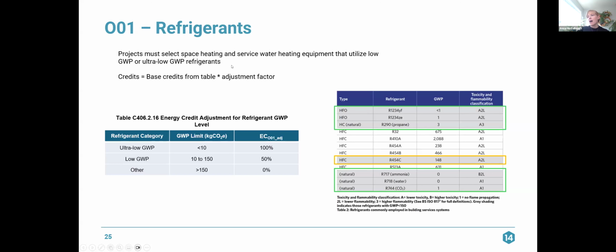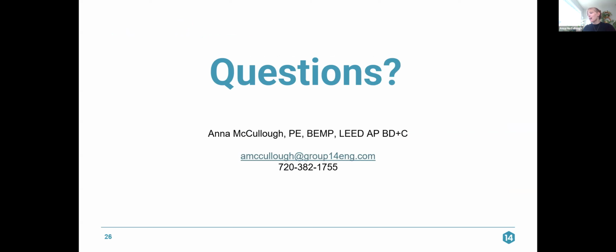And then the ultra low GWPs are going to be these: propane, R1234ZE and YF, ammonia, water, and CO2. And I do want to highlight that this is the requirement for space heating and service water heating equipment. So if your rooftop units are using R1234YF, but your water heaters are using, let me think of a good one, 410A or R454A, you can't comply. It has to be all of the refrigerants in the building. That was it. So if there are any questions, please let me know.